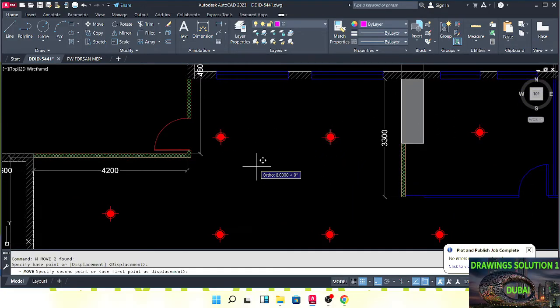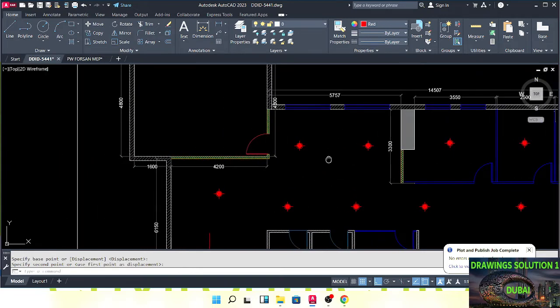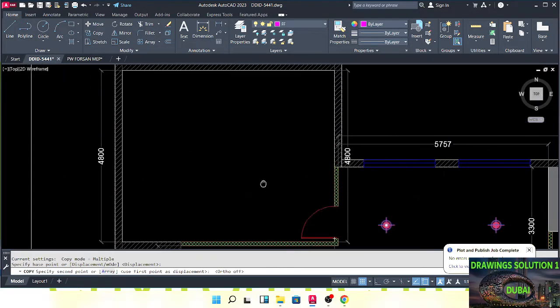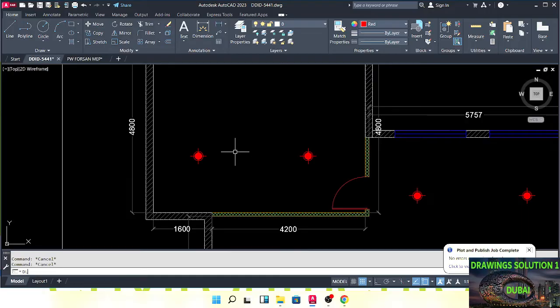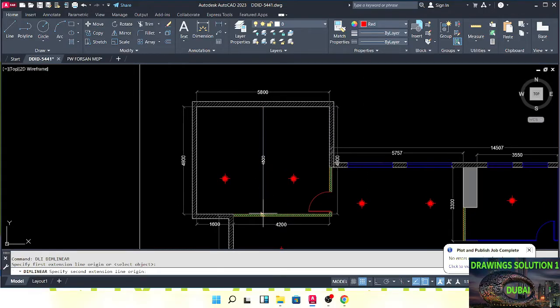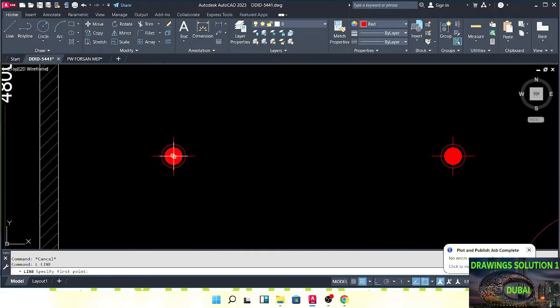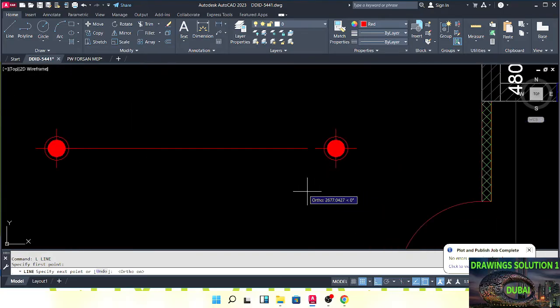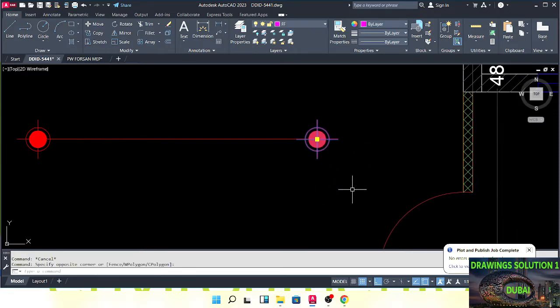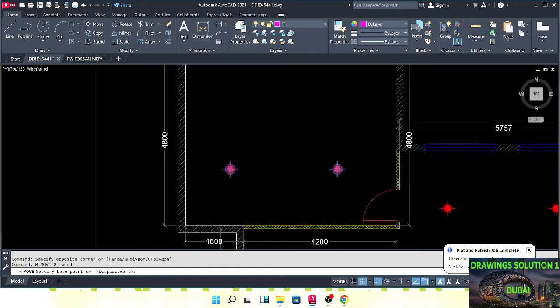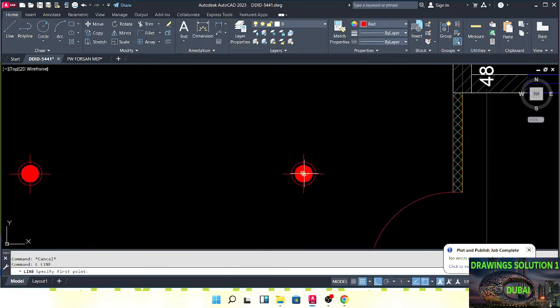Please shift these two sprinklers to the center of this area. This is done — two sprinklers in this office. We can see this one is 480, so we can make four sprinklers. We can facilitate 3 meters, so we can make two sprinklers here and two sprinklers in the big office.